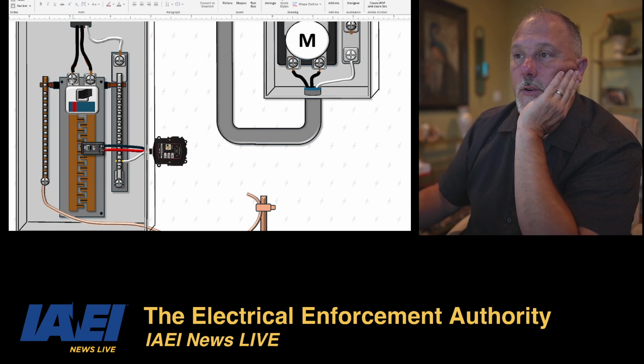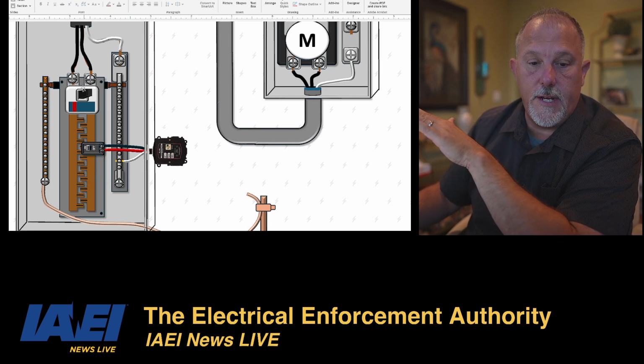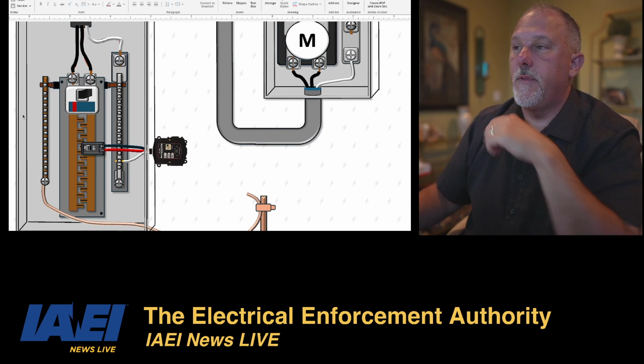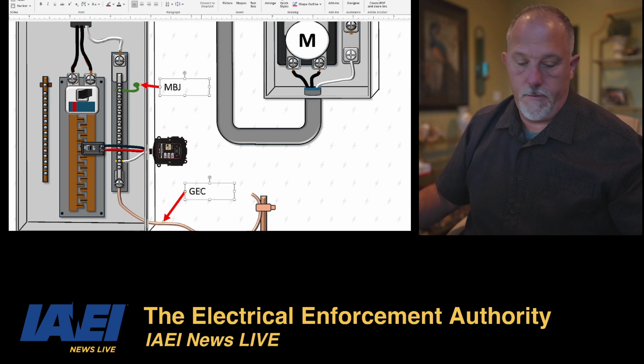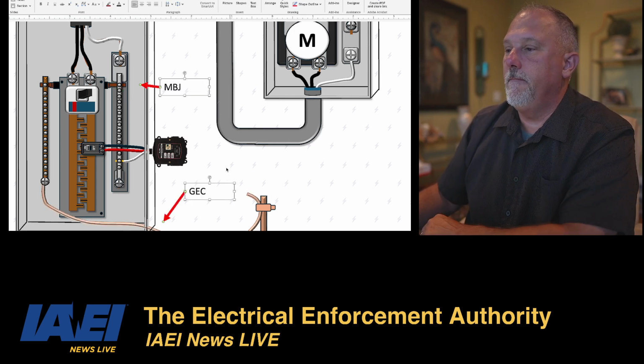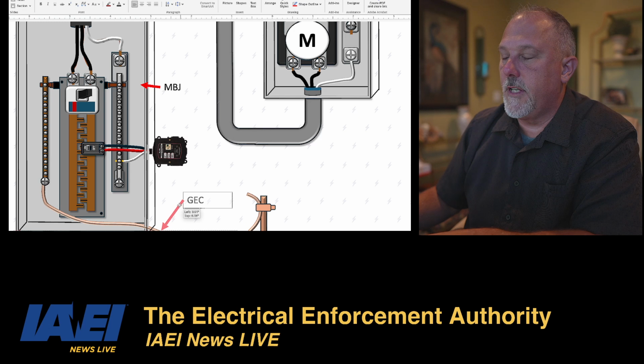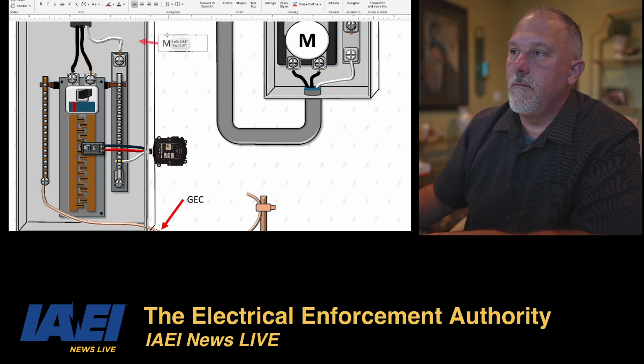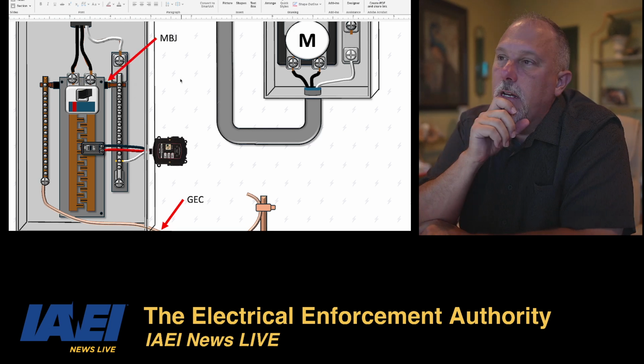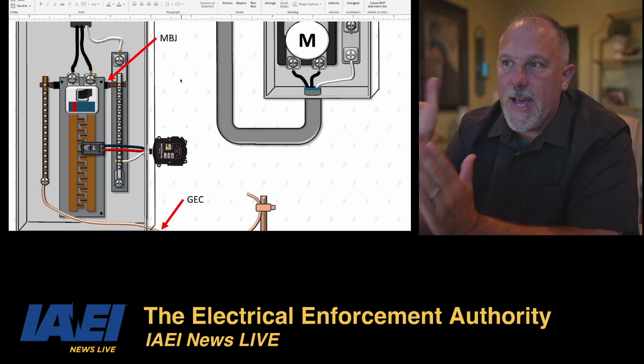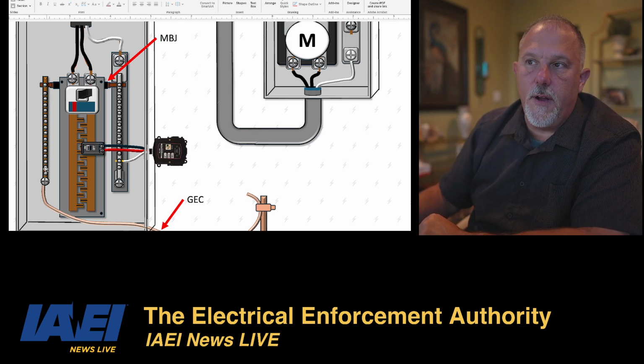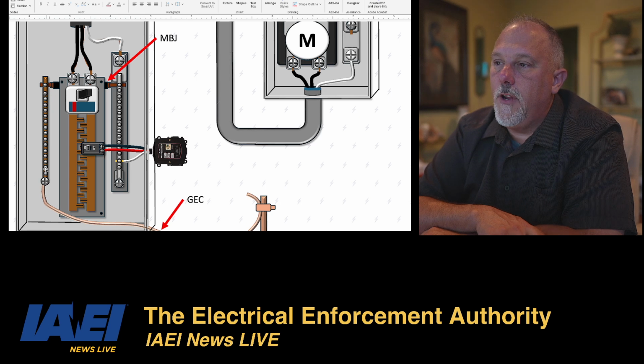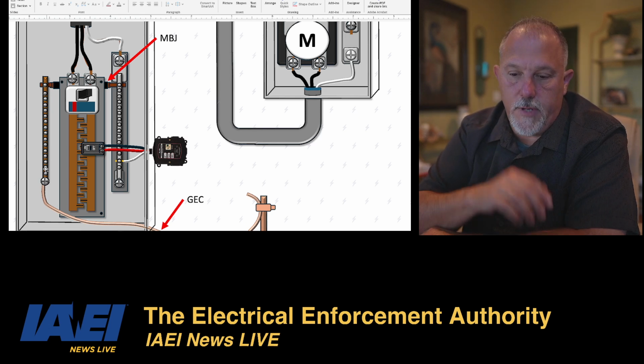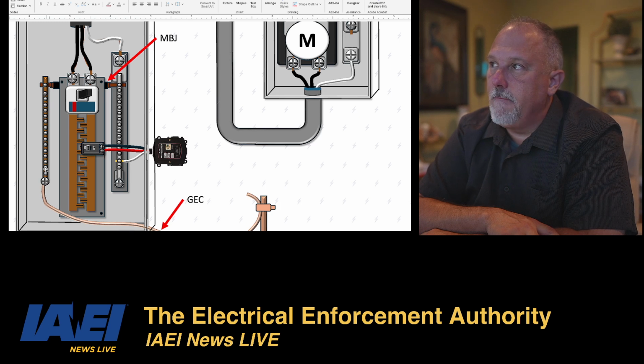So because that physical bar exists right here, let's go grab the text from the other. Copy, paste. Okay, so this is still my grounding electrode conductor. My main bonding jumper is right there. And because it is a physical bar, it's not the back pan, I am permitted to land the grounding electrode conductor on this grounding bar, and not on the neutral bar. So again, make sure everything is correct there. All right. It's like poetry in motion. It's beautiful.